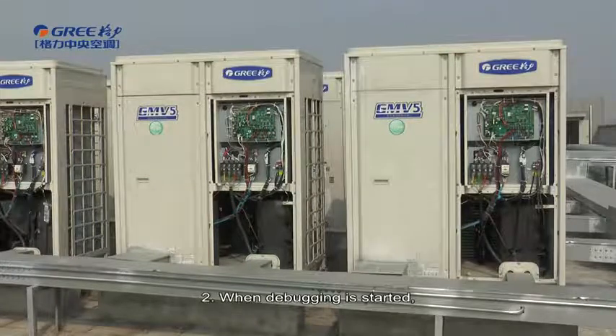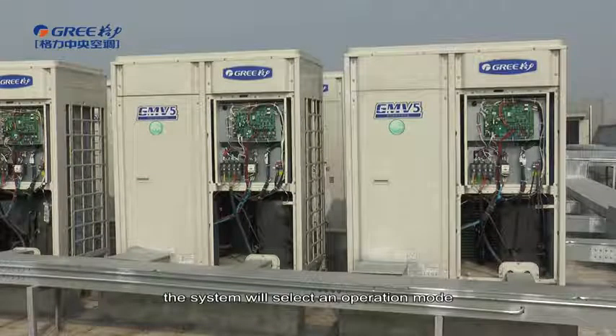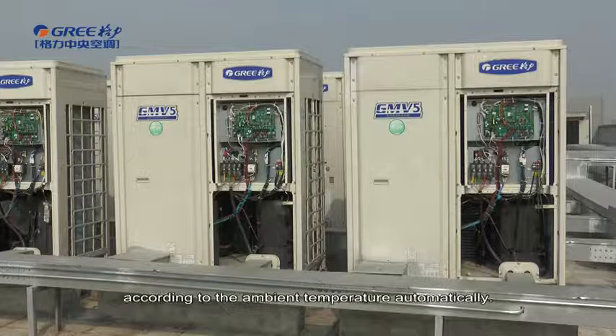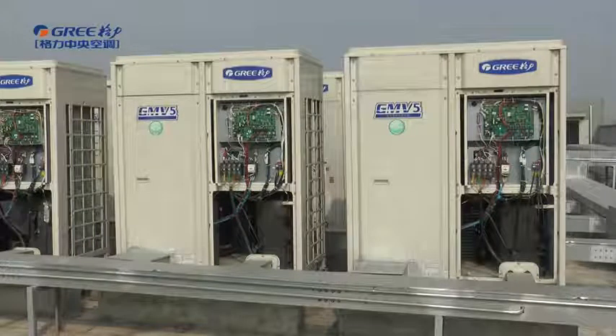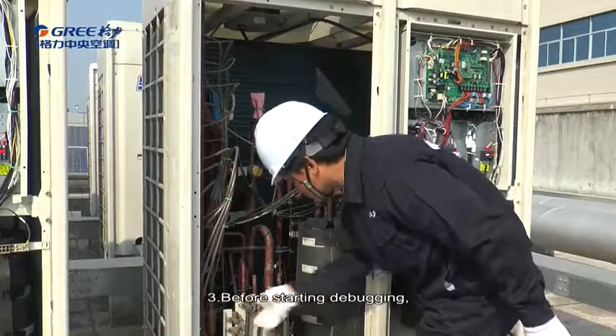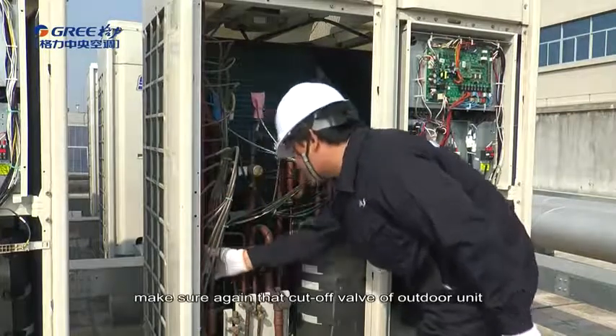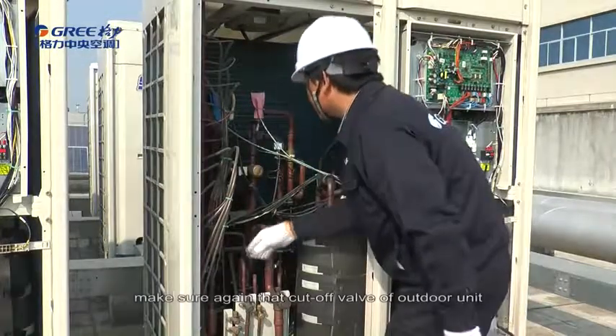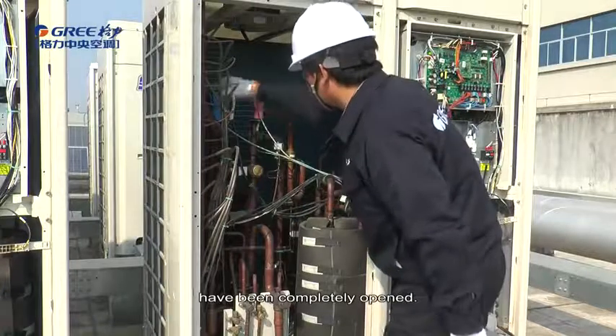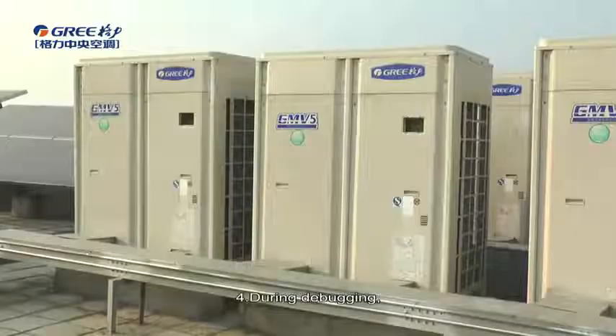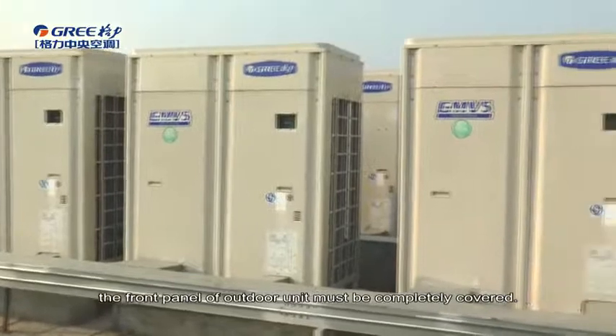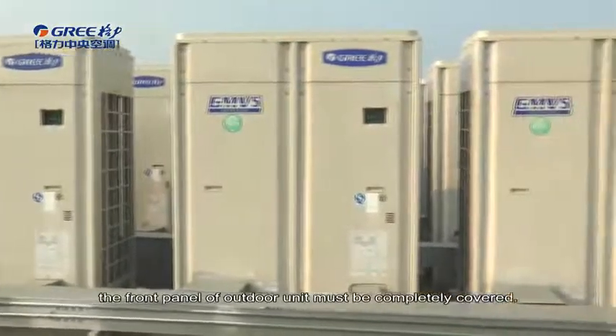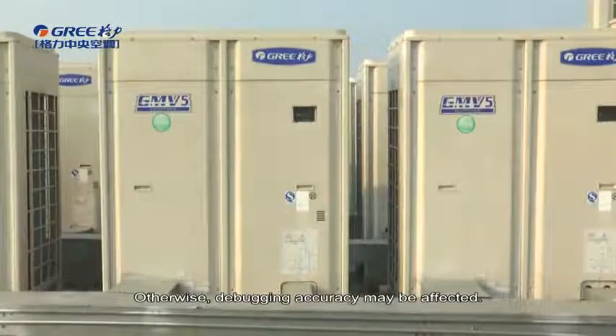Second, when debugging is started, the system will select an operation mode according to the ambient temperature automatically. Third, before starting debugging, make sure again the cut-off valve of outdoor unit have been completely open. Fourth, during debugging, the front panel of outdoor unit must be completely covered, otherwise debugging accuracy may be affected.